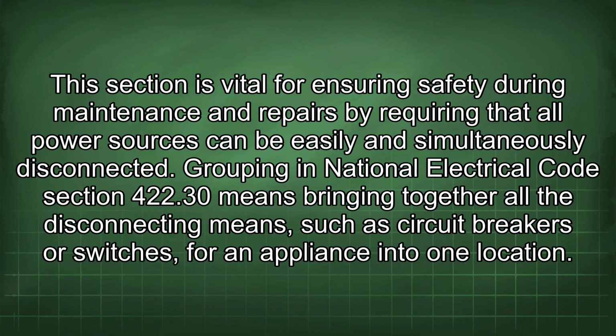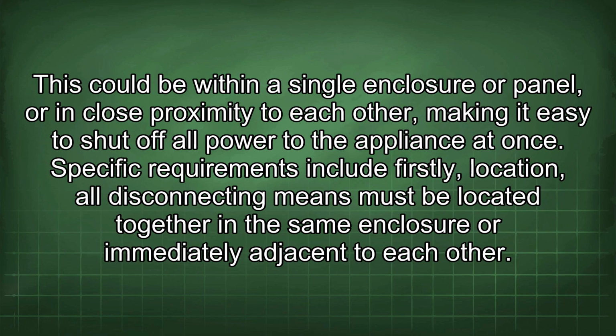Grouping in National Electrical Code Section 422.30 means bringing together all the disconnecting means, such as circuit breakers or switches, for an appliance into one location. This could be within a single enclosure or panel, or in close proximity to each other, making it easy to shut off all power to the appliance at once. Specific requirements include: firstly, location.